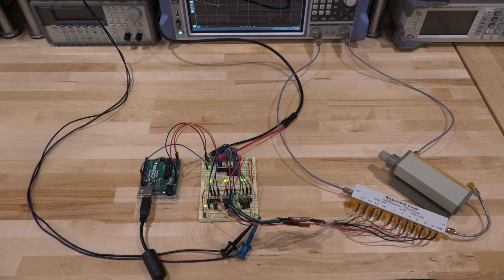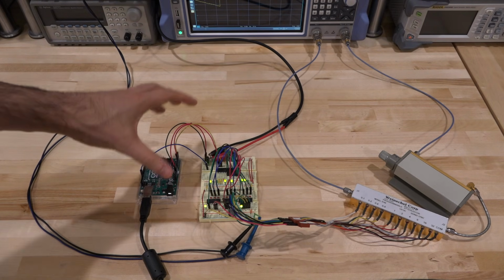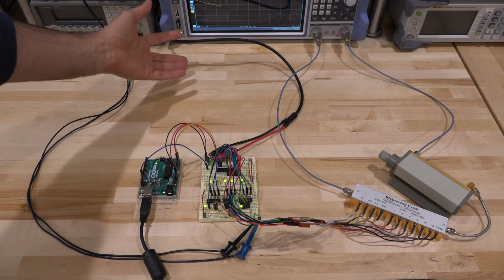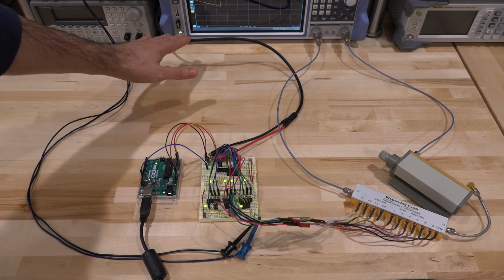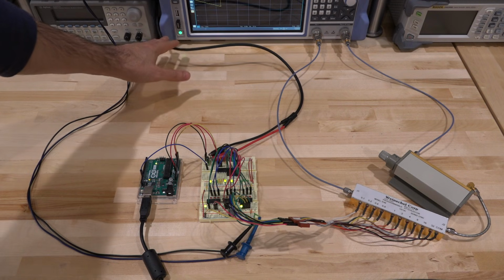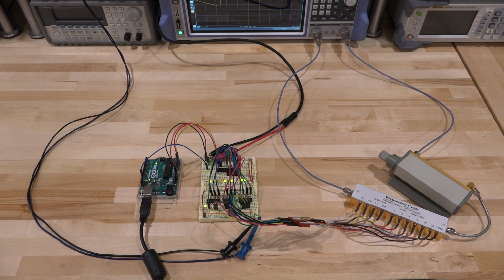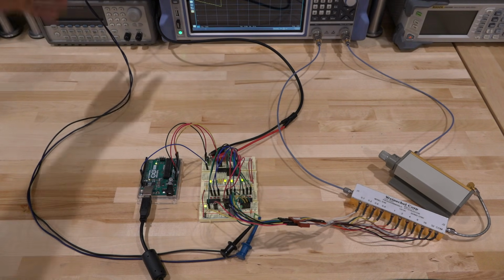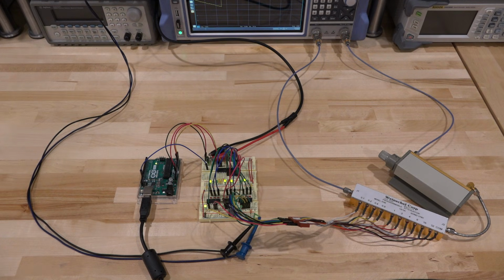Now, I also want to make this measurement very precise and time predictable, so I'm going to configure the network analyzer with an external trigger. The trigger itself is also provided by the Arduino and is using this cable right here. So this goes to the back of the instrument to the external trigger port, and we can use that to trigger the unit. There is really nothing else going on, some power supply coming from the outside to power all the I/O expander and the high voltage H-bridge drivers to give the 12 volts to the attenuator.